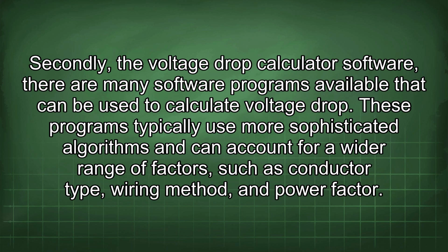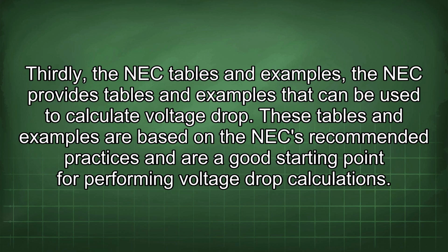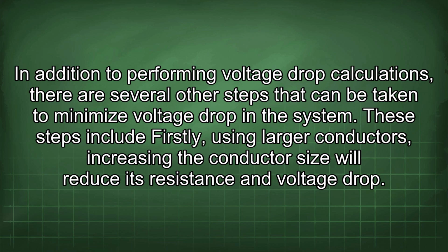There are many software programs available that can be used to calculate voltage drop. These programs typically use more sophisticated algorithms and can account for a wider range of factors such as conductor type, wiring method, and power factor. Thirdly, the NEC tables and examples. The NEC provides tables and examples that can be used to calculate voltage drop. These tables and examples are based on the NEC recommended practices and are a good starting point for performing voltage drop calculations. In addition to performing voltage drop calculations, there are several other steps that can be taken to minimize voltage drop in the system.